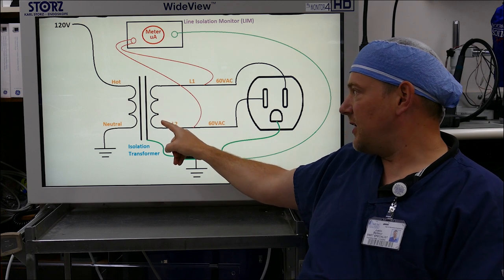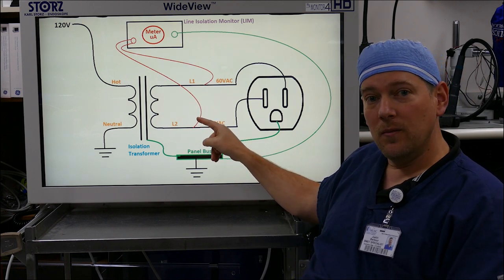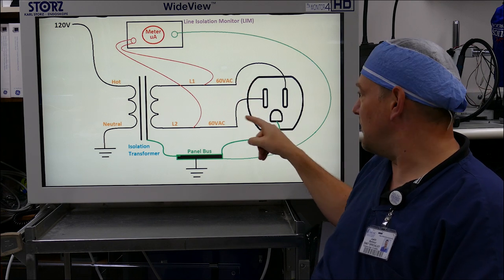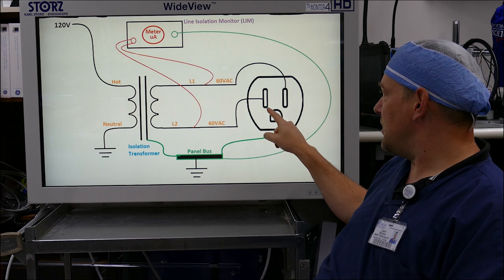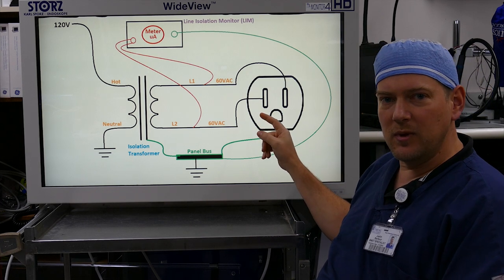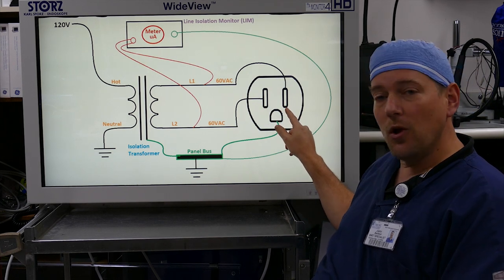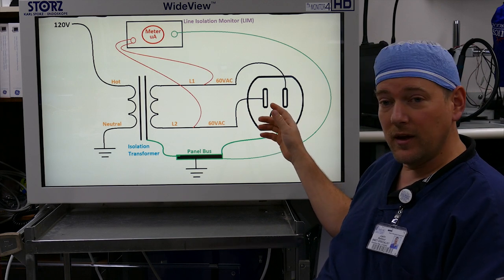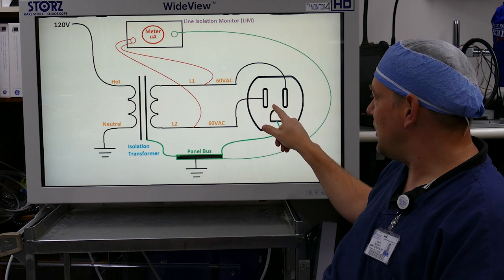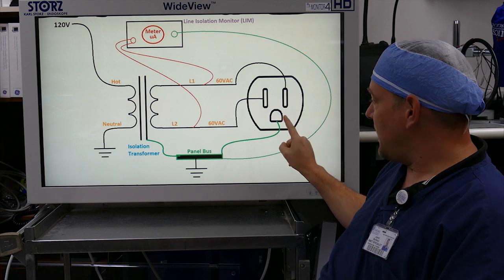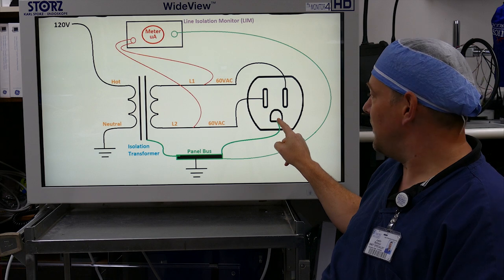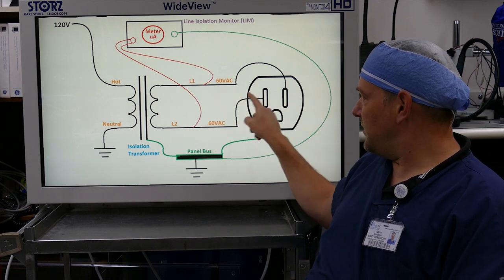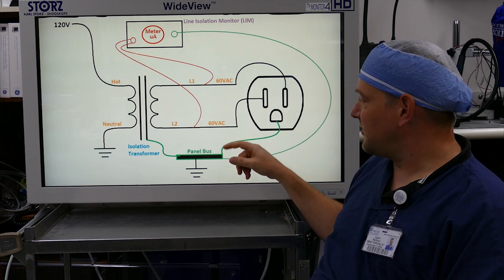Over here on the secondaries you'll have L1 and L2. Both of the secondaries will be at 60 volts potential. So normally in an electrical outlet you have a large opening which would be your neutral, a small opening which would be your hot, and then you have your ground. While in operating room electrical you have 60 volts, 60 volts, and you have ground. Ground, if you can see here, has nothing to do with the other two. It's completely separate.